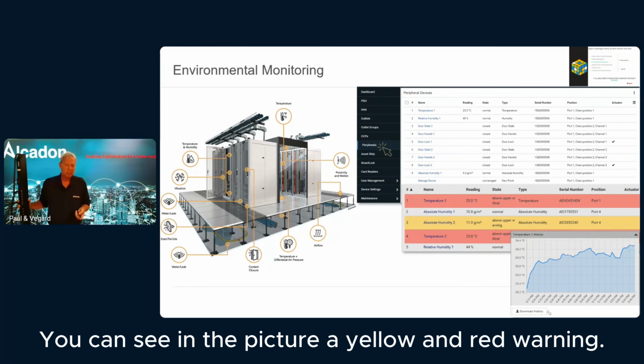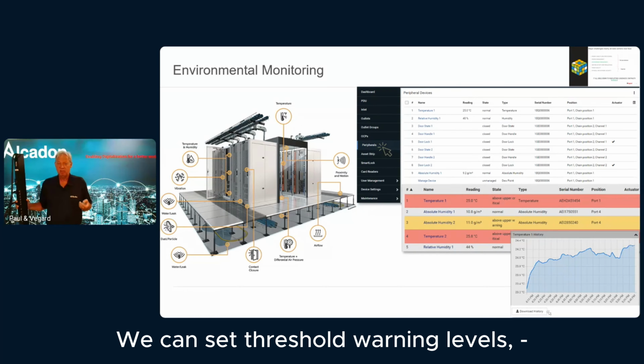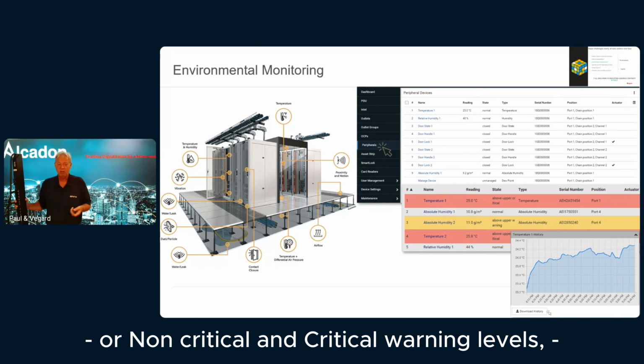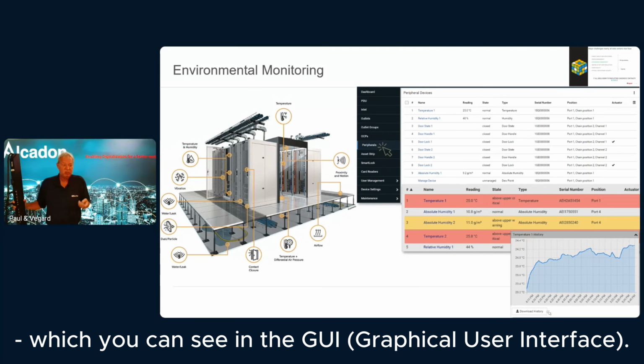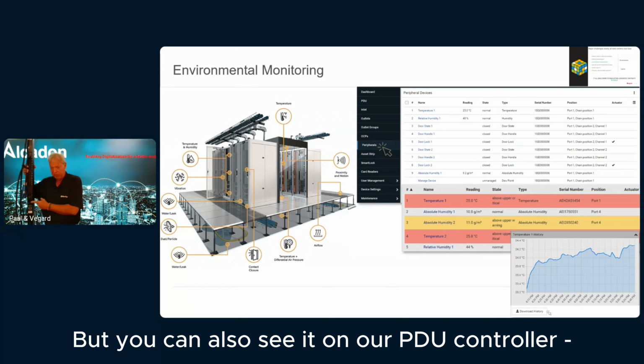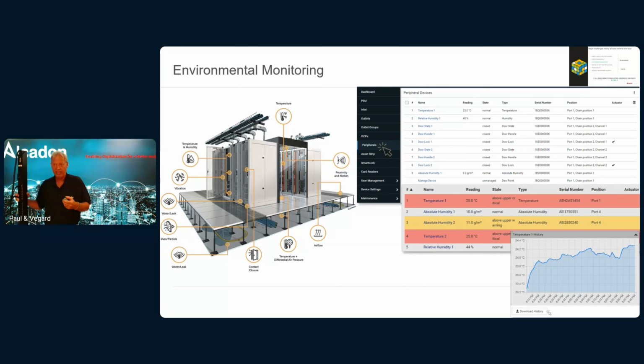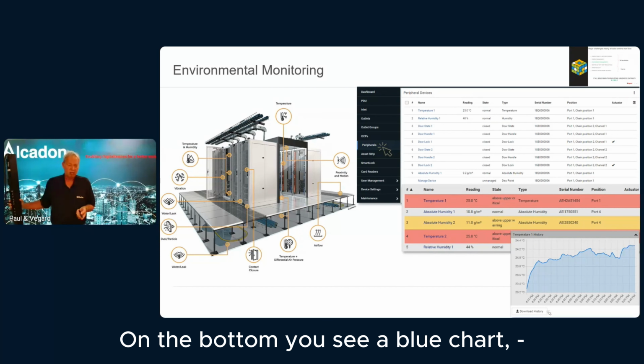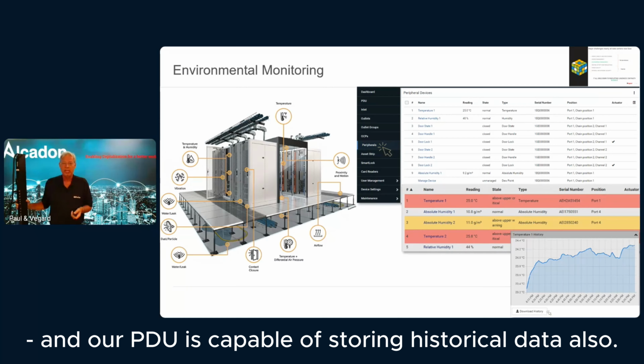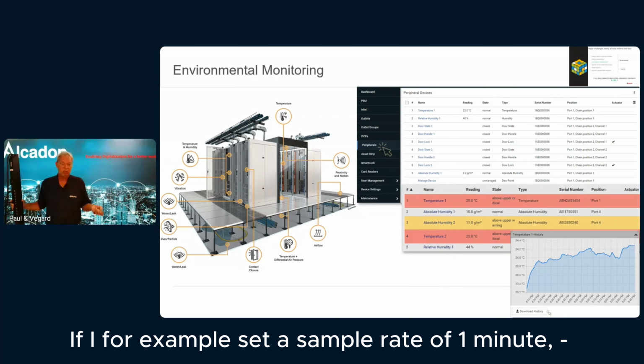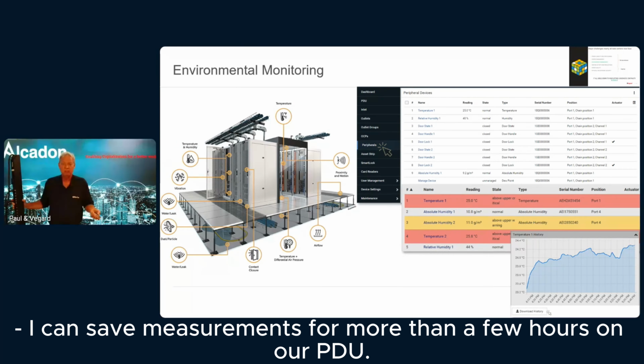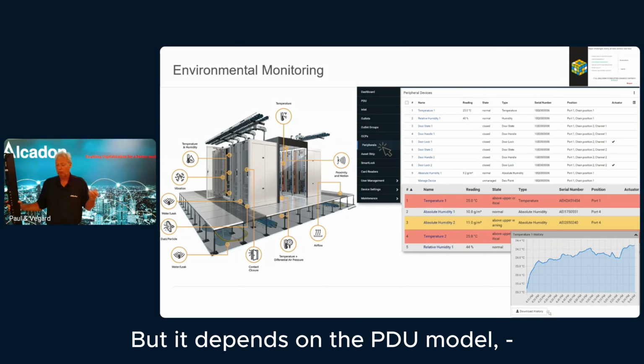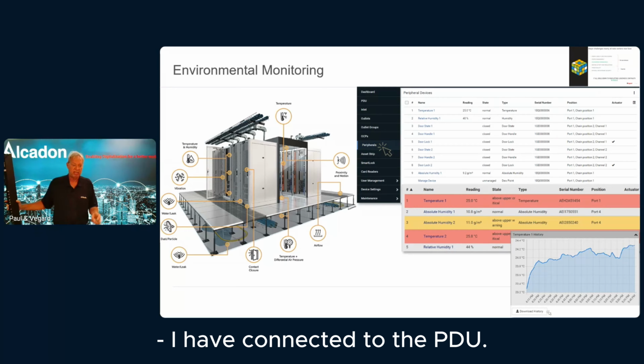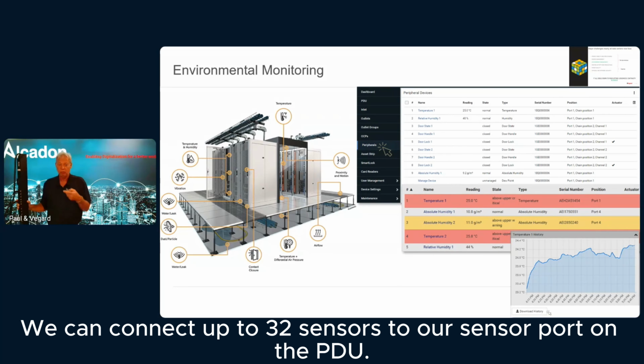You can see in the picture a yellow and red warning. We can set threshold warning levels, so-called yellow and red, or non-critical and critical warning levels, which you can see in the GUI, but you can also see it on our PDU controller with the same yellow and red colors. On the bottom, you see a blue chart, and our PDU is capable of storing historical data also. If I, for example, set a sample rate of 1 minute, I can save measurements for more than a few hours on our PDU, but it depends on the PDU model. It depends also on how many sensors I have connected to the PDU. Again, we can connect up to 32 sensors to our sensor port on the PDU.